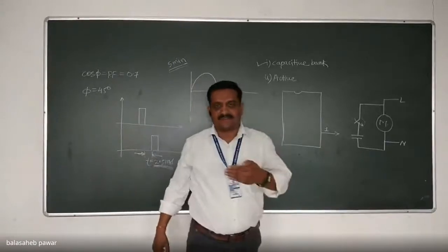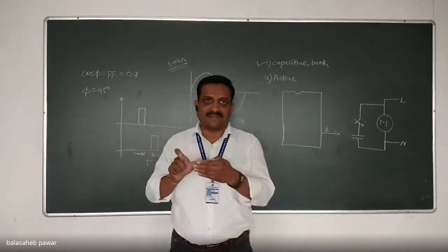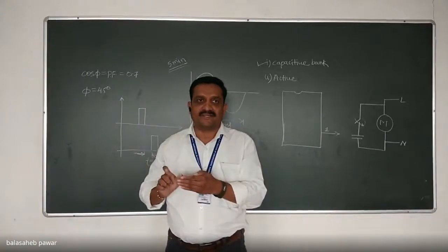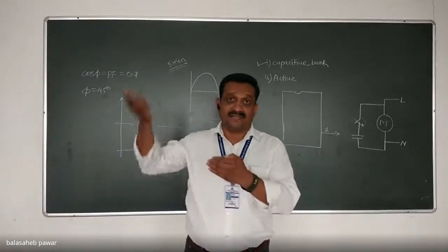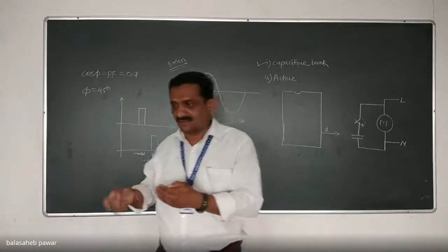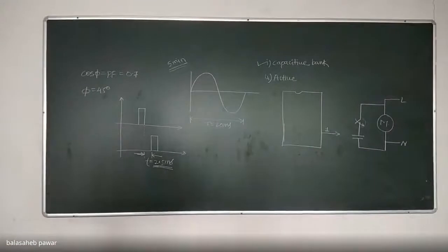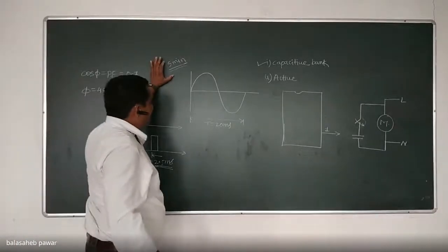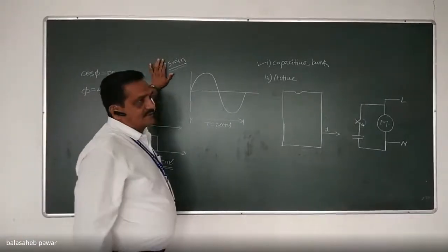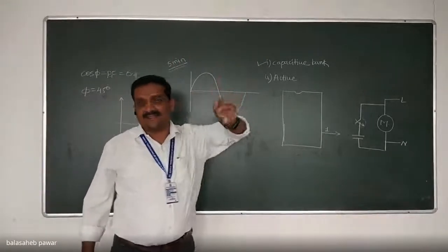Suppose the power factor is currently checked, and if it is above 0.7, no issue, our controller should check it again after 5 minutes. So the delay for the timely measurement of that power factor will be 5 minutes. All these things you have to note down at your end, because while developing the program, you have to consider all these things, that delay and everything.